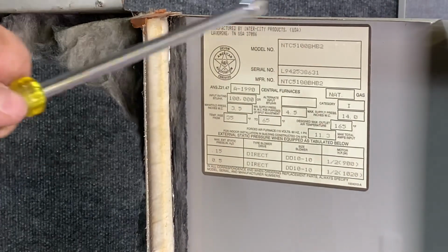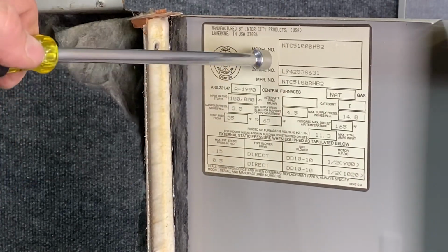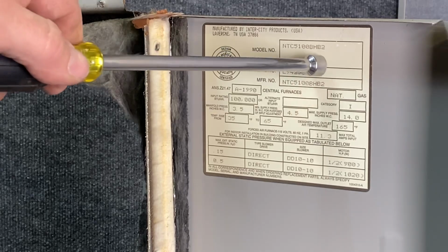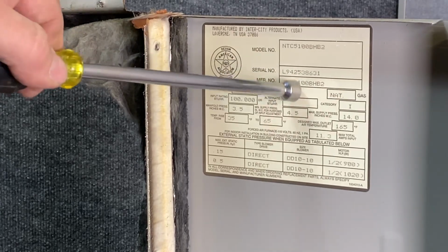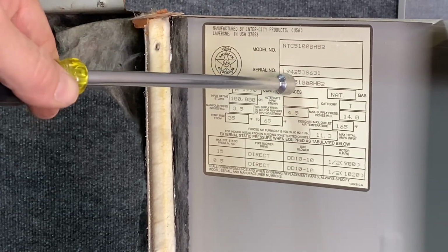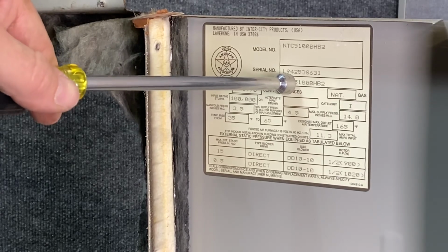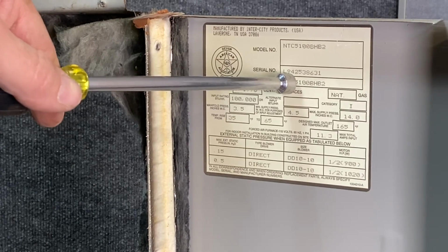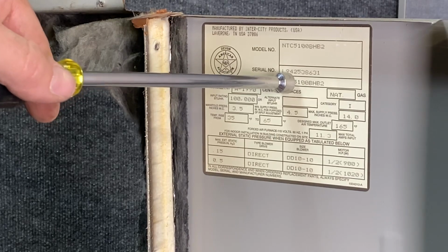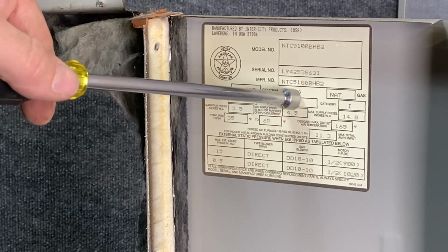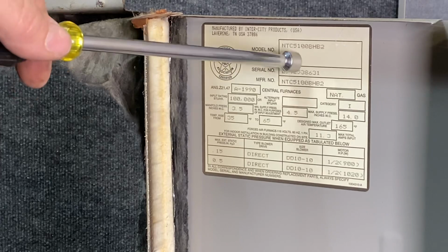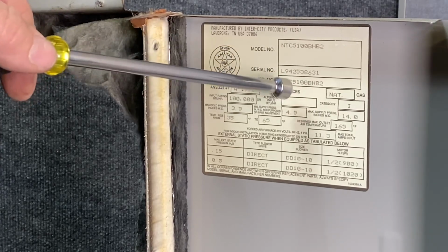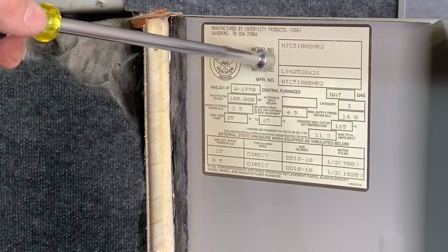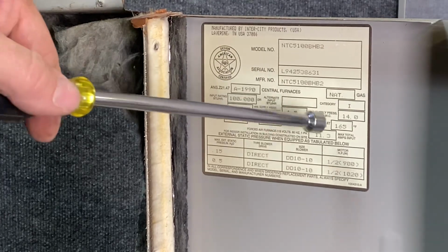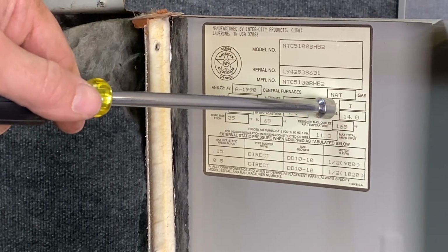Okay, so here's the tag of our unit, a lot of very important information. We'll have our model number, which should be recorded on every single service call. We'll have the serial number. The serial number is going to give us the age. And this particular brand, L94, this is a 1994 model furnace. So it's old, ready to be replaced. It has a manufacturer number, which is almost identical to the model number. In this case, it is identical. You want to make sure you write down any discrepancies between the model and the manufacturer number. This unit is manufactured for natural gas.